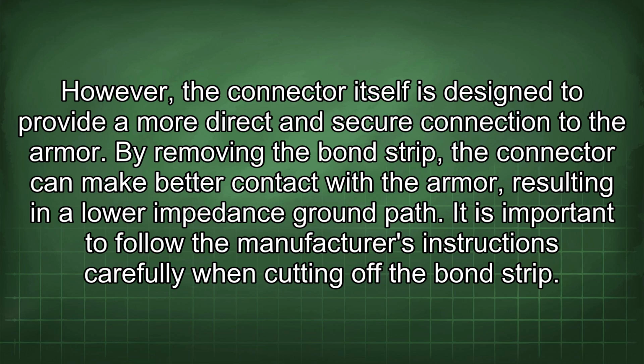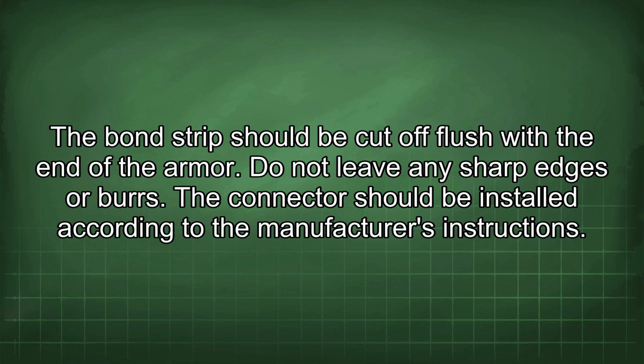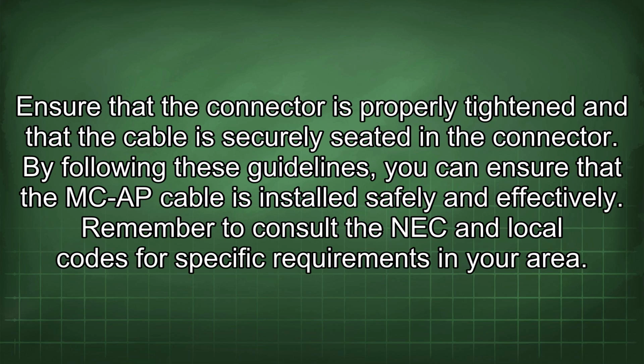path. It is important to follow the manufacturer's instructions carefully when cutting off the bond strip. The bond strip should be cut off flush with the end of the armor. Do not leave any sharp edges or burrs. The connector should be installed according to the manufacturer's instructions. Ensure that the connector is properly tightened and that the cable is securely seated in the connector.